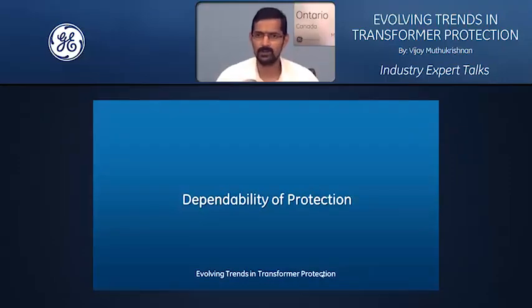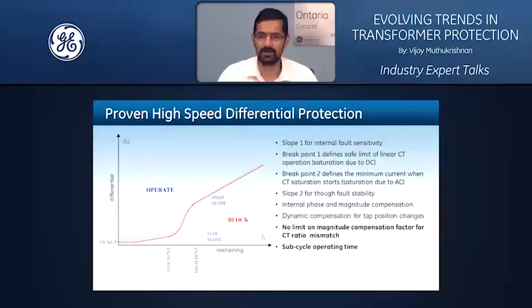Now we will touch upon the details of each of those areas we talked about, such as the various pillars of best-in-class transformer protection. The first one on the reliability dimension is the dependability of protection. The core of the transformer protection relay is the transformer differential protection. The traditional approach has been a dual slope characteristic to do differential protection.